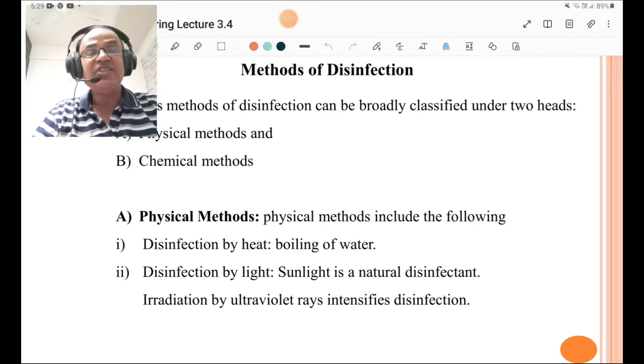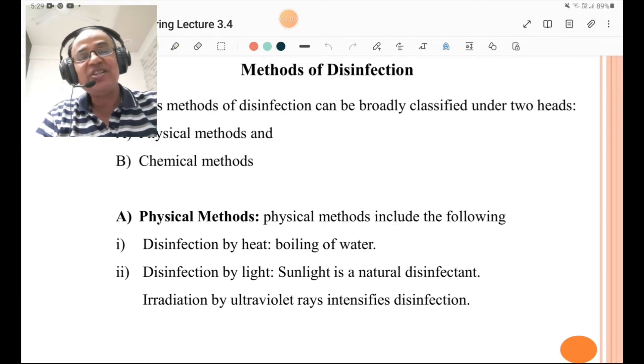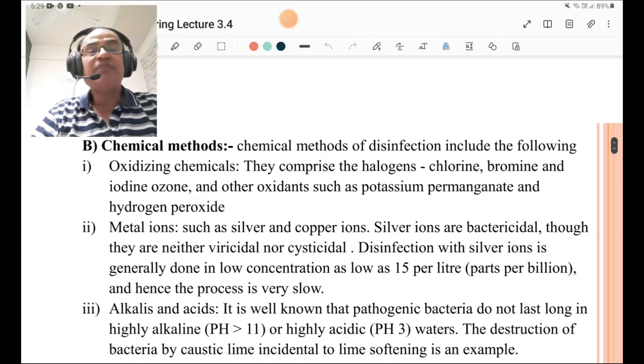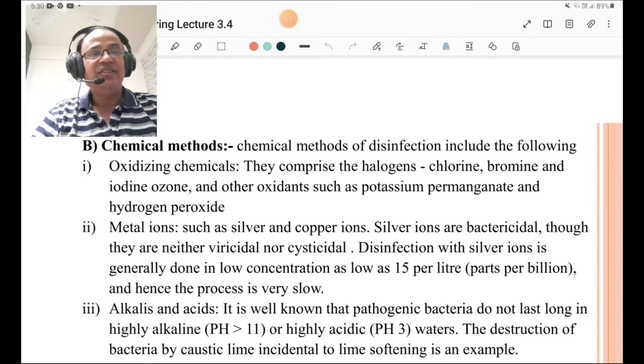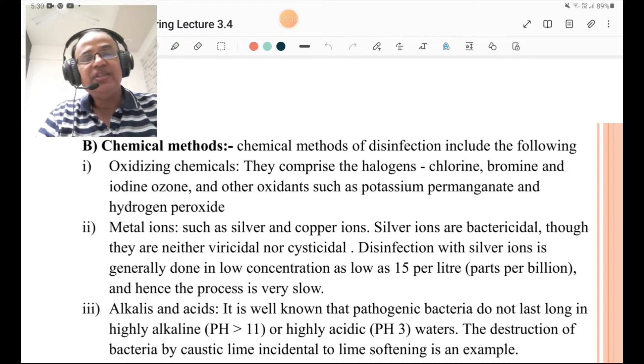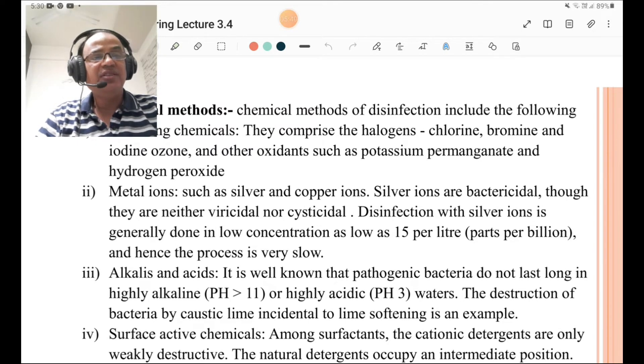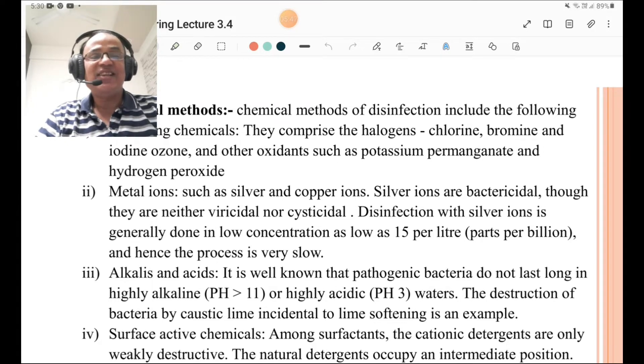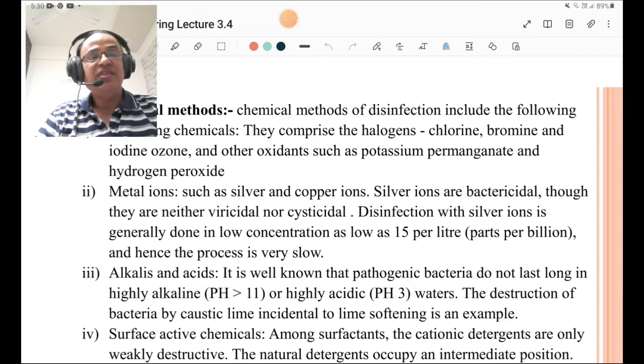Irradiation by ultraviolet rays also intensifies disinfection, so using sunlight for disinfection is also a physical method. Chemical methods of disinfection include the following: first, oxidizing chemicals, which comprise the halogens — chlorine, bromine, and iodine — ozone, and other oxidants such as potassium permanganate and hydrogen peroxide. Metal ions such as silver or copper ions are bactericidal, though they are neither virucidal nor cysticidal. Disinfection with silver ions is generally done at a low concentration of about 15 parts per billion, and hence the process is very slow.